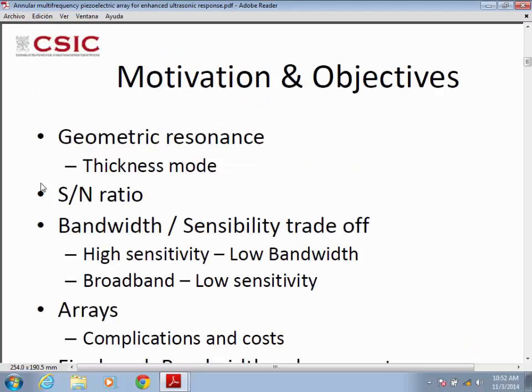A typical approach to design a piezoelectric transducer is to rely on geometric resonances, typically in the thickness mode, in order to achieve a better signal to noise ratio. This thickness mode provides a lot of gain at one specific frequency, but usually you have to manage a trade-off between this sensitivity and the bandwidth. As long as you have a high sensitivity, you will have a lower bandwidth, and so on. So usually arrays are designed to get both worlds accomplished.